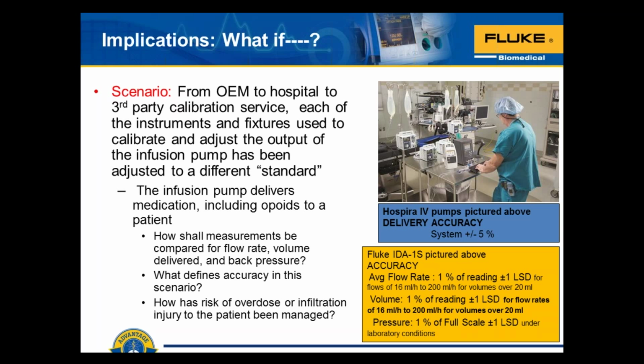So I've put down accuracies that we publish about our IDA-1S. This is our little portable battery-operated one-channel infusion device analyzer. So the flow rate accuracy that we specify is 1% of reading plus or minus one least significant digit for flows of 16 milliliters per hour to 200 milliliters per hour for volumes over 20 milliliters. The volume accuracy is 1% of the reading plus or minus one least significant digit for flow rates of 16 to 200 milliliters per hour as long as the volume's over 20 milliliters. The pressure accuracy is a percentage of full scale plus or minus one least significant digit, which is how we assess the accuracy for our measurements on our test instrument as we deliver it to you.